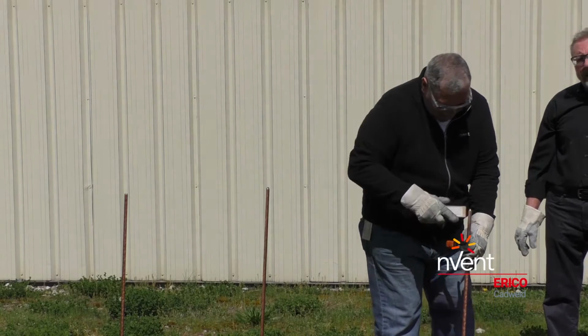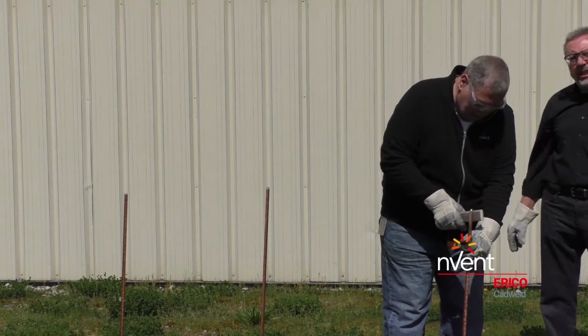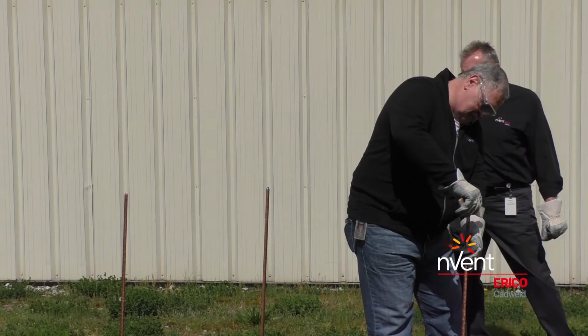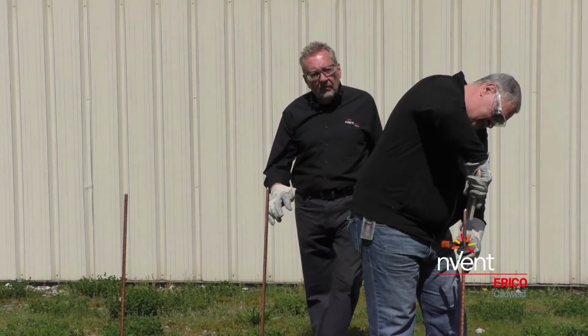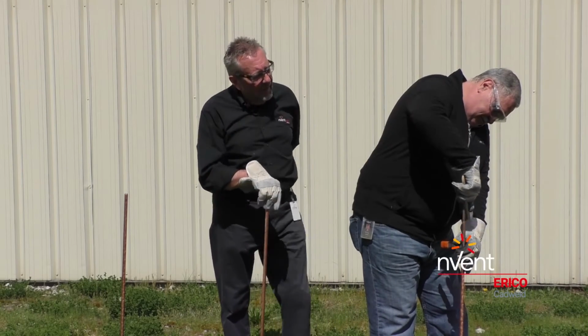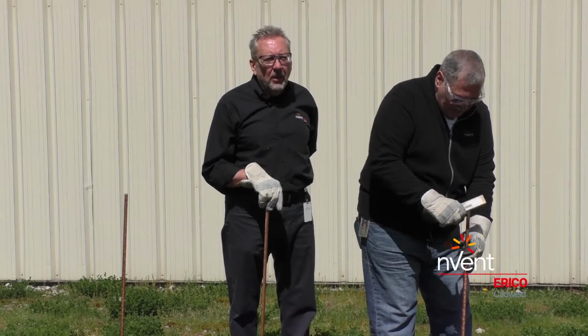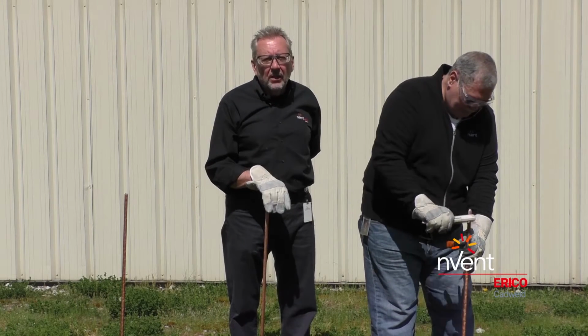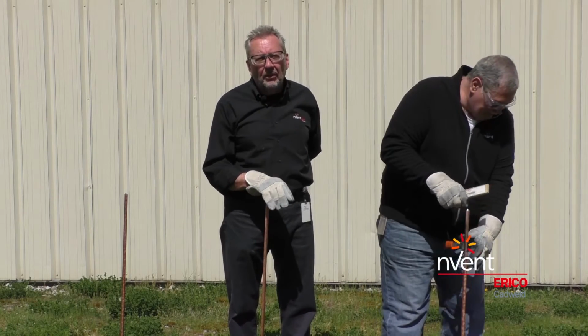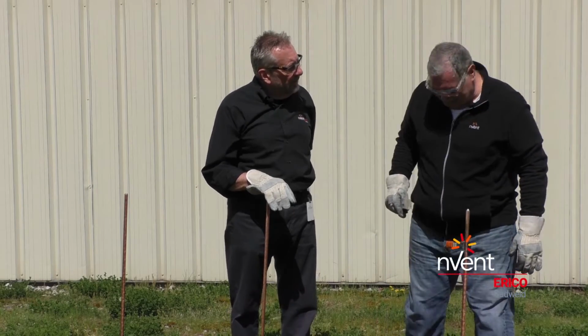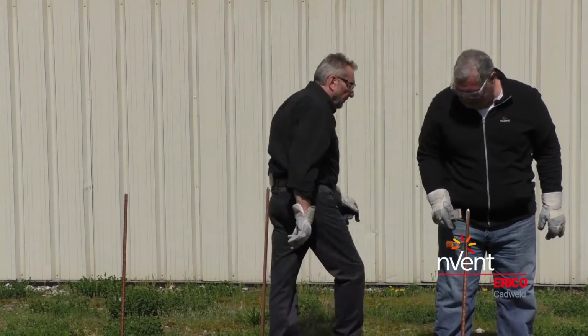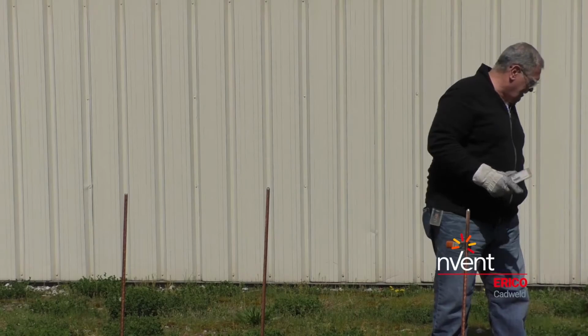There could be oil on the end of the rod. In real life field installations, there will be mud and water and all kinds of things, so we always use the torch to dry the conductor and the top of the rod just to be safe. I'll go get the torch, and the cable.